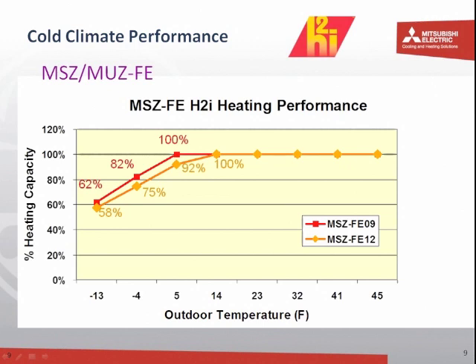We talked earlier about the ability for these systems to operate even in cold climates, and this is just a graphic representation. There are several different sizes of what we call our hyperheat unit, which have this capability to operate at low ambient temperatures. The two depicted here are the 9,000 BTU and 12,000 BTU models. As you can see, as low as 5 degrees, the 9,000 BTU model is still producing 100% of its rated capacity, which actually tends to be a bit higher than the cooling capacity. It's a 9,000 BTU rated cooling capacity, about 11,000 BTU rated heating. And so it's continuing to produce that.